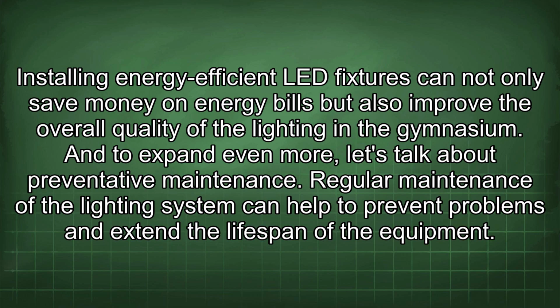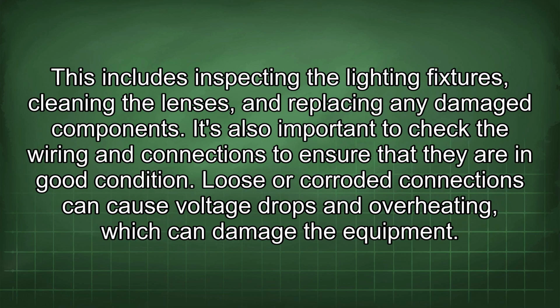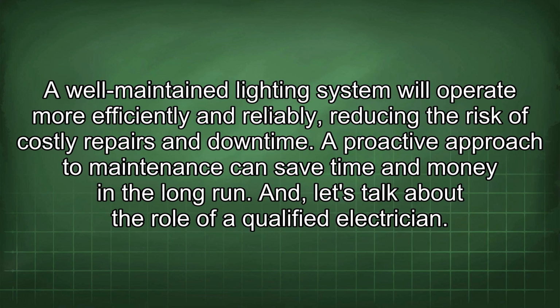And to expand even more, let's talk about preventative maintenance. Regular maintenance of the lighting system can help to prevent problems and extend the lifespan of the equipment. This includes inspecting the lighting fixtures, cleaning the lenses, and replacing any damaged components. It's also important to check the wiring and connections to ensure that they are in good condition. Loose or corroded connections can cause voltage drops and overheating, which can damage the equipment. A well-maintained lighting system will operate more efficiently and reliably, reducing the risk of costly repairs and downtime. A proactive approach to maintenance can save time and money in the long run.